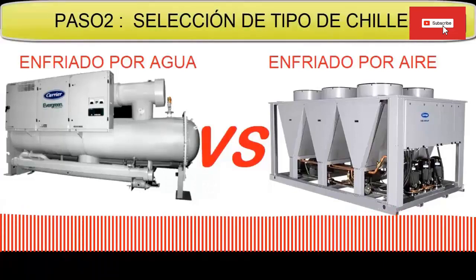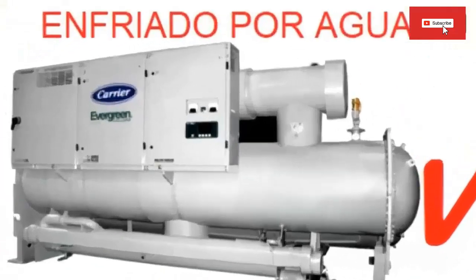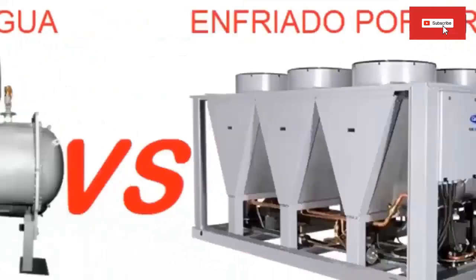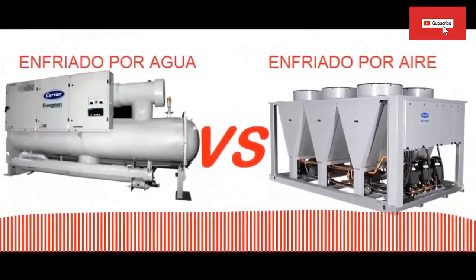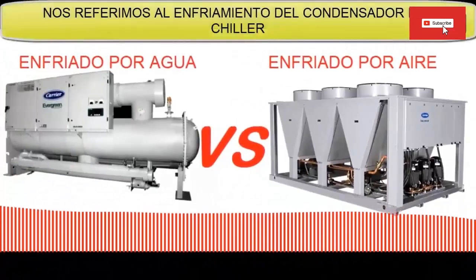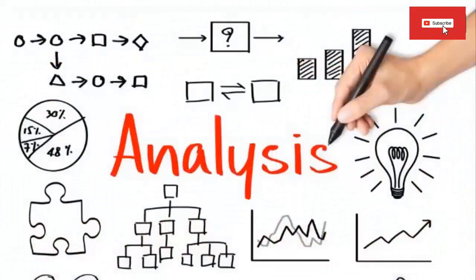The first choice of the type of machine is based on whether a water-cooled chiller or an air-cooled chiller is better. Let's remember that we need the chiller to remove the heat from the water and turn it into ice water. But the heat gained by the chiller must be expelled in its condenser. For this we have two options, the cooling of its condenser by water or by air. To make this decision, we must analyze each type separately.